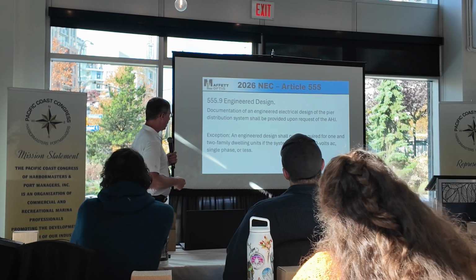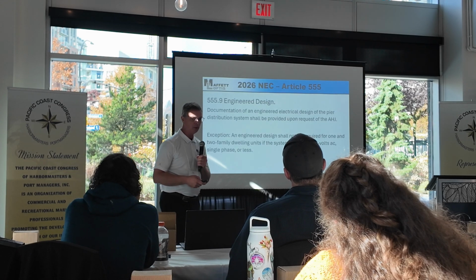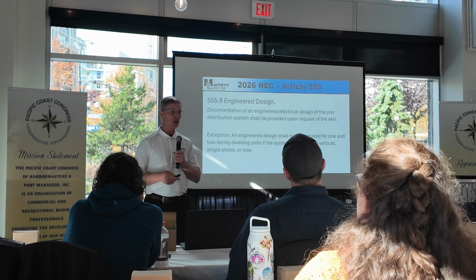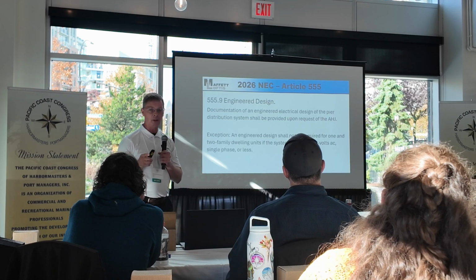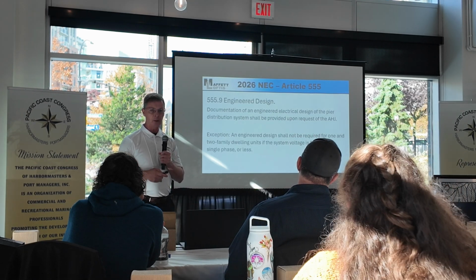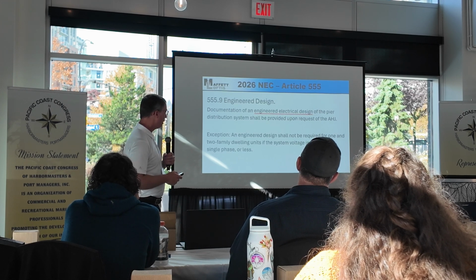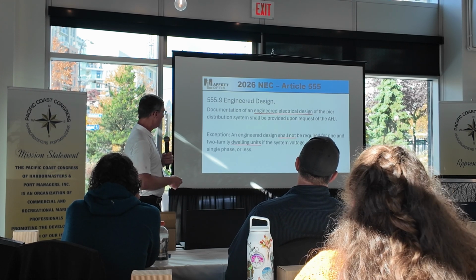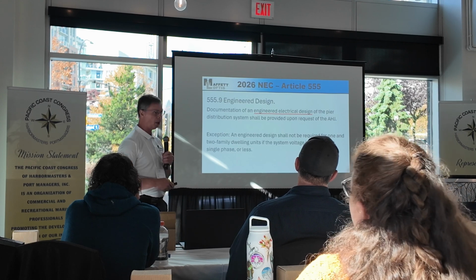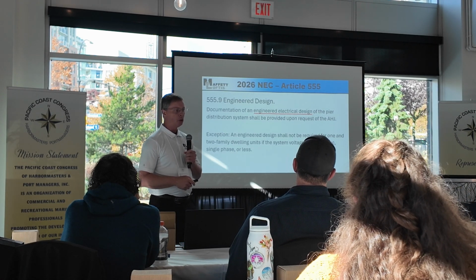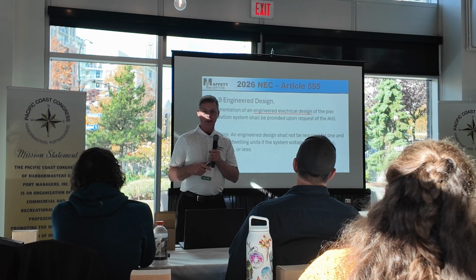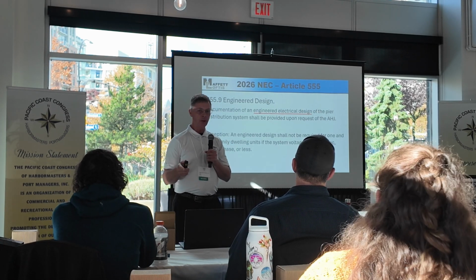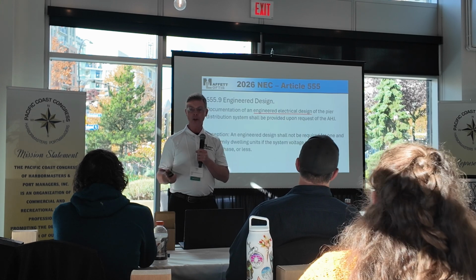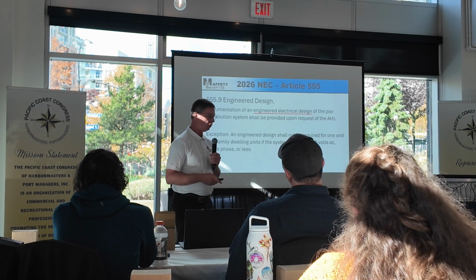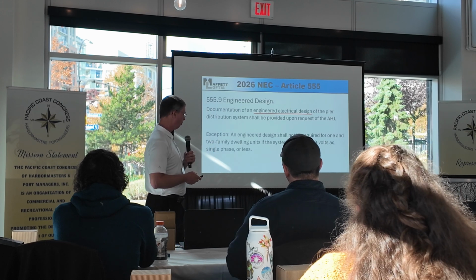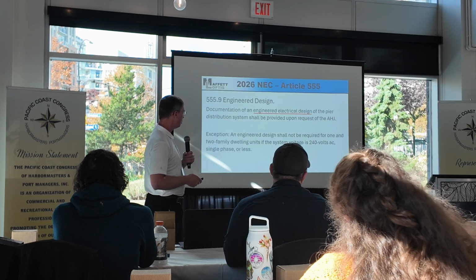Now, 555.9 is going to require, or has the opportunity of requiring, engineering for marinas. And this is not mandatory unless the AHJ, the electrical inspector, says, I want to see electrical plans. Up to this point, this has not been in the code, but engineering design is required basically upon request of the AHJ, which is authority having jurisdiction. So if the electrical inspector sees that, well, this is a very complicated marina, or I've had trouble with the electrician that's here, he can say, I want engineered plans. And then the electrician, maybe through a design build, or the marina operator would have to get engineered plans.